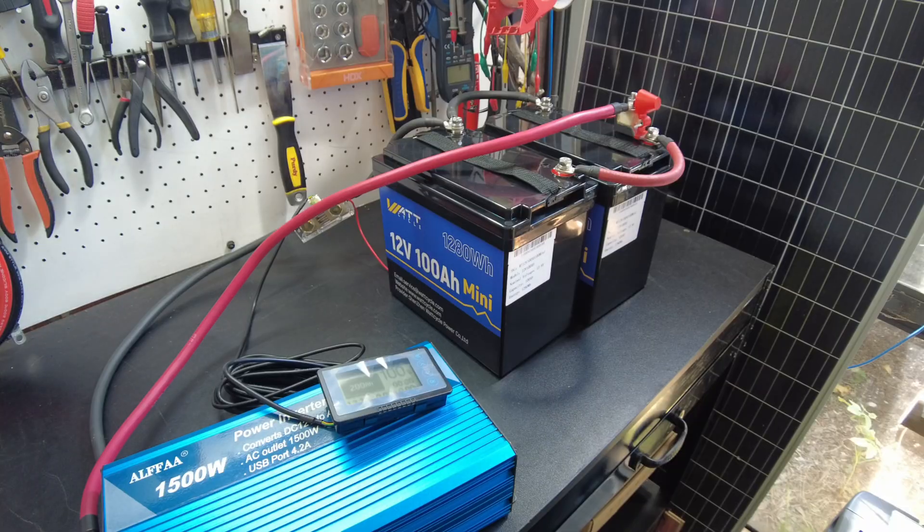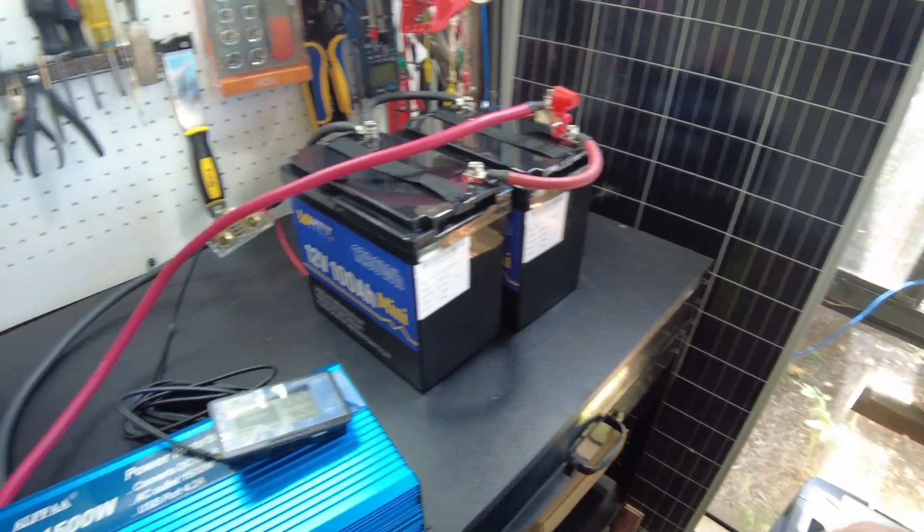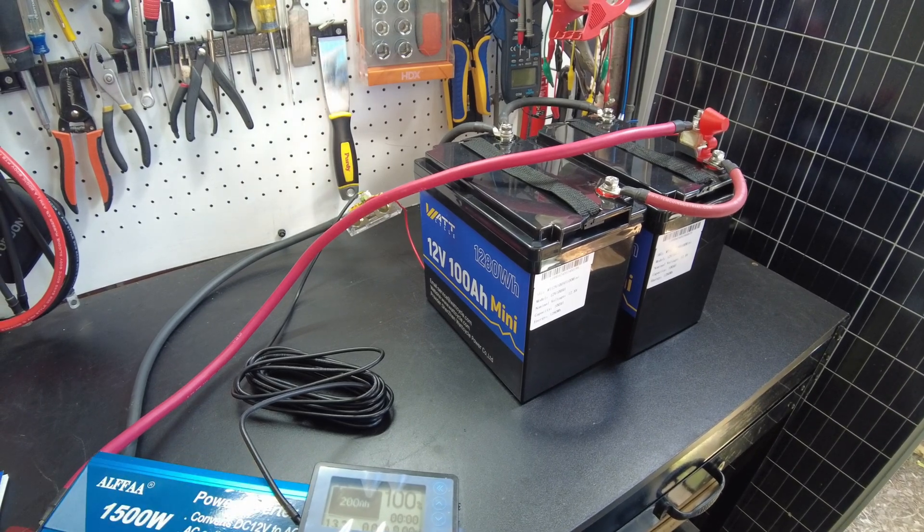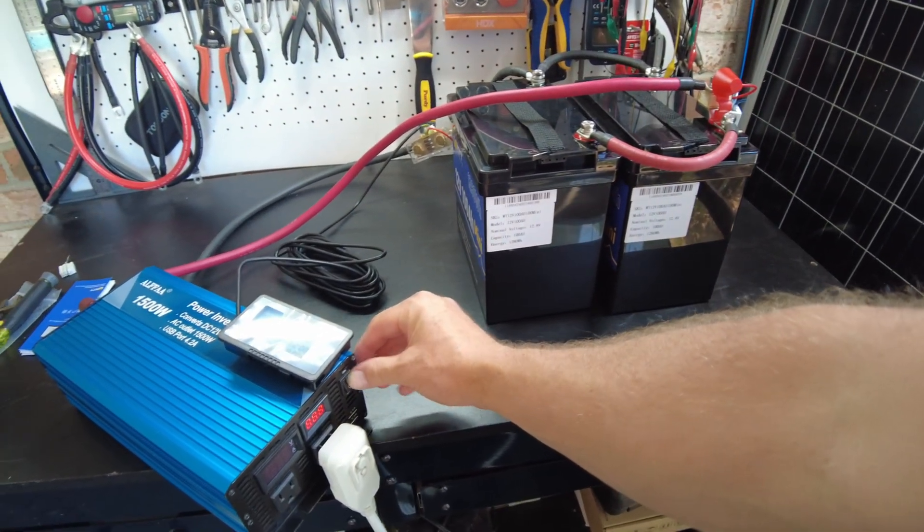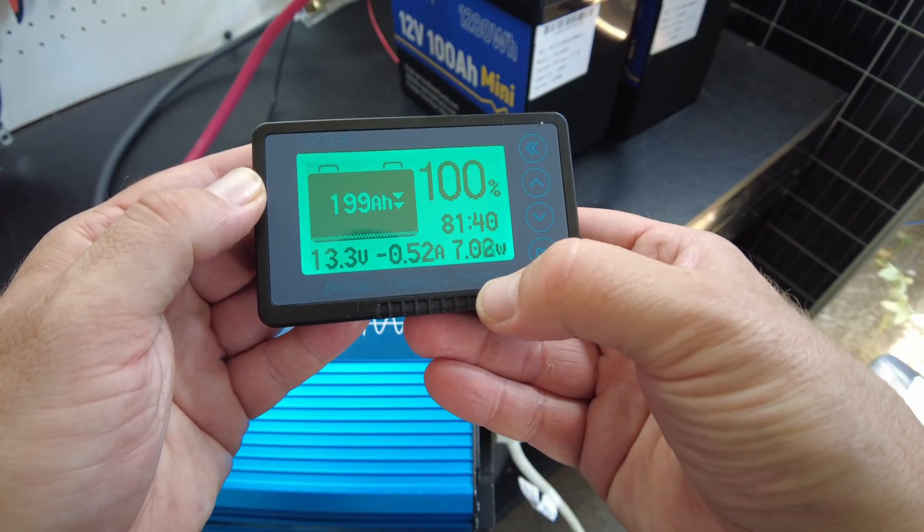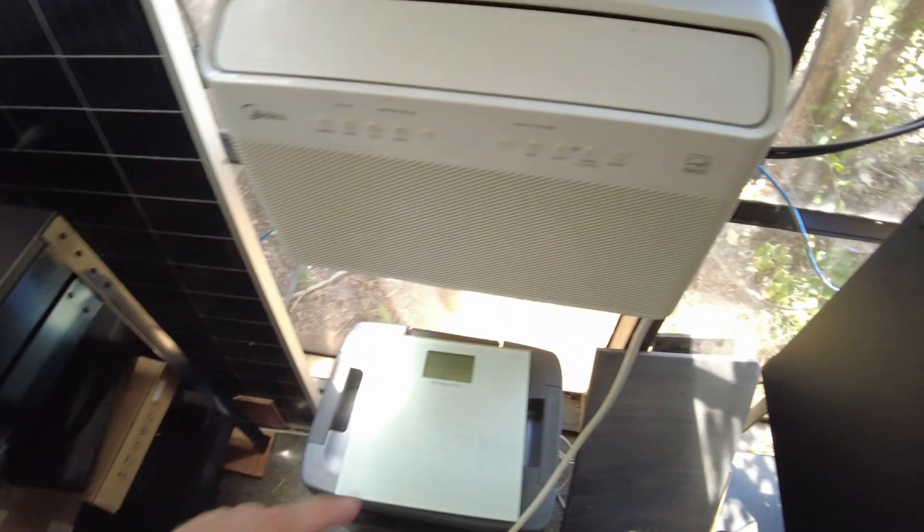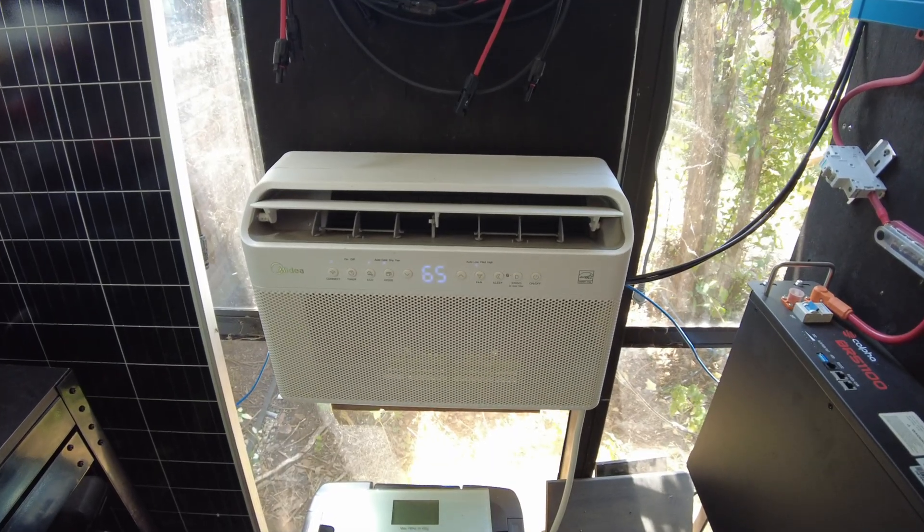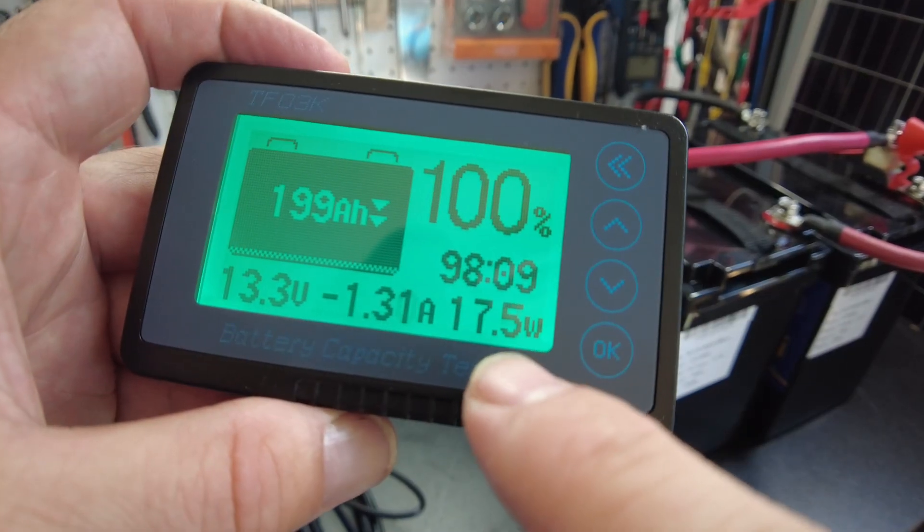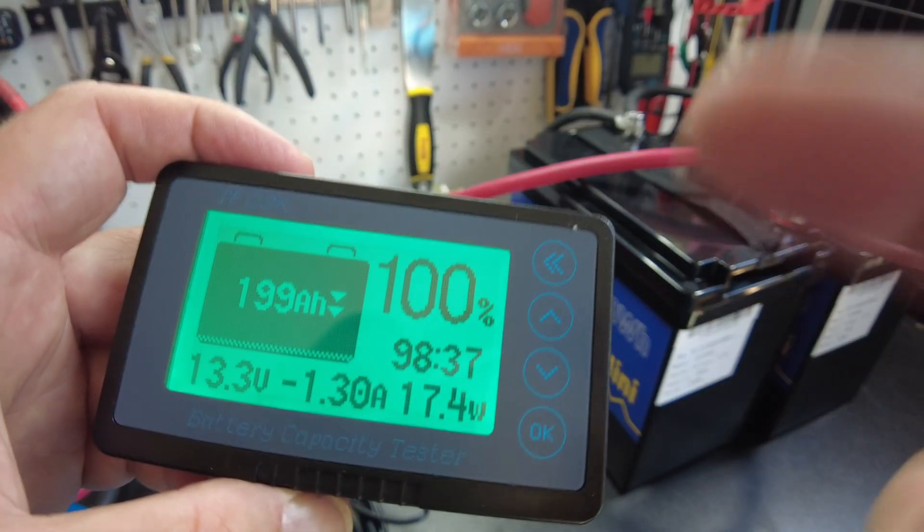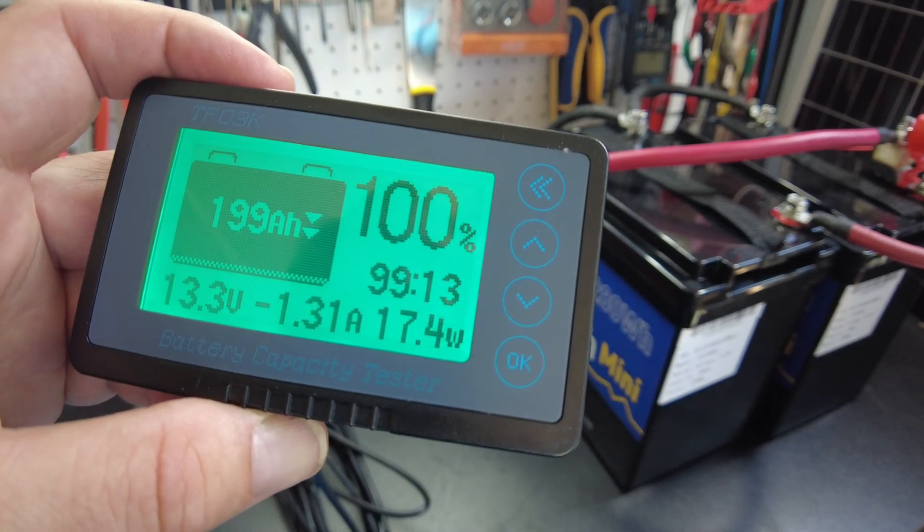So let's hook something up to our inverter here. I'm going to hook up this air conditioner and run a load. Let's turn the power on to the inverter. There we go. And it's showing that we are pulling seven watts. So that's going to be the idle consumption of the inverter. Let's go ahead and turn on the air conditioner. It's showing 17.4 watts. The compressor is not on yet on the air conditioner, so we're going to have to wait a minute for that to kick on.